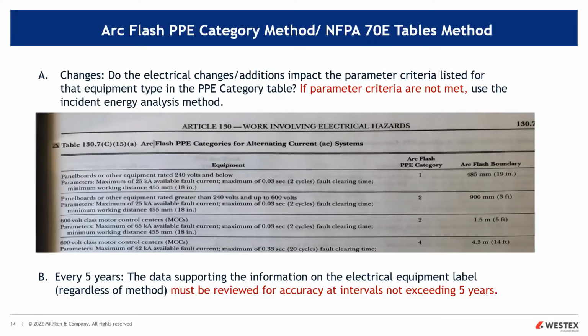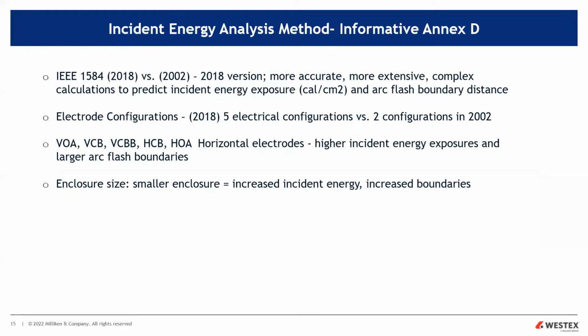So every 5 years, or when you make changes, no matter what method you're using, you need to review the data on the labels, because if the info on the labels is incorrect, the PPE is going to be incorrect. Now, if you're doing the incident energy method, AKA the arc flash study method, you can go to Informational Annex D of NFPA 70E. Basically, what most companies do, or the latest and greatest, is utilize IEEE 1584, and you want to look at the latest edition, which is the 2018.